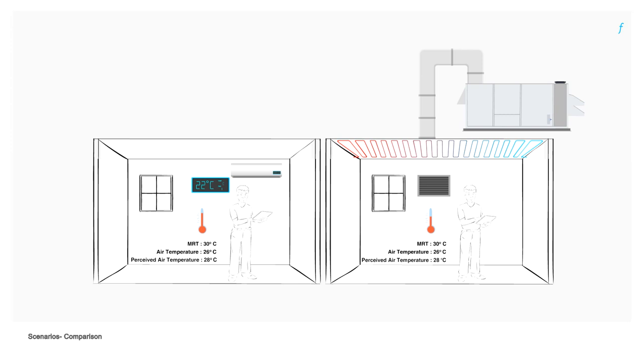A room with a regular air-based cooling system has a higher mean radiant temperature and therefore needs a low room air temperature to make the occupants feel comfortable. A radiant-cooled room, however, has a lower mean radiant temperature and can provide the same cooling effect at a relatively higher room air temperature.